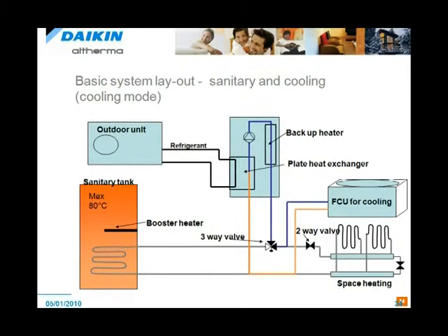There's a three-way valve going for priority domestic hot water that is available either in the cooling or the heating mode. And you'll see a two-way valve there to assure that chilled water is not going into your space heating. The wiring diagrams for that are in your instruction manual in the hydro box. I really recommend that online you can go and look at our technical session and you'll see the installation manuals. There's detailed instructions within that.